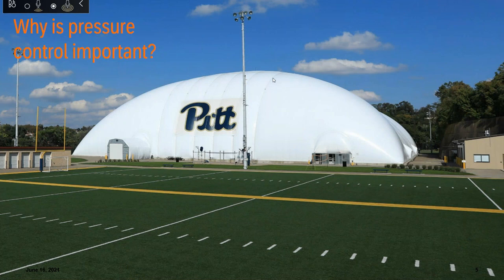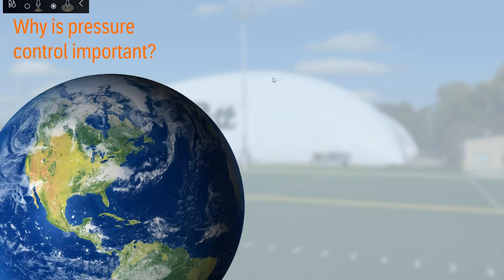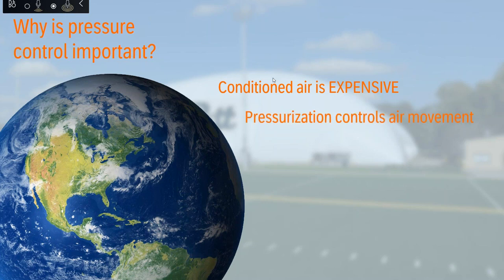Why is pressure control important? Looking at the University of Pittsburgh football practice facility sports dome — pressure within these sports domes is very, very critical. I really want to relate this back to energy efficiency. Conditioned air is not cheap — it's actually pretty expensive. As we bring in air from the outside, that air is not conditioned, so you have to change the temperature, remove moisture, push the air through filters, and clean the air. When this gets into our facilities, we need to ensure that this air does not escape. We can use pressurization to ensure that the air stays within certain zones and within our facilities.